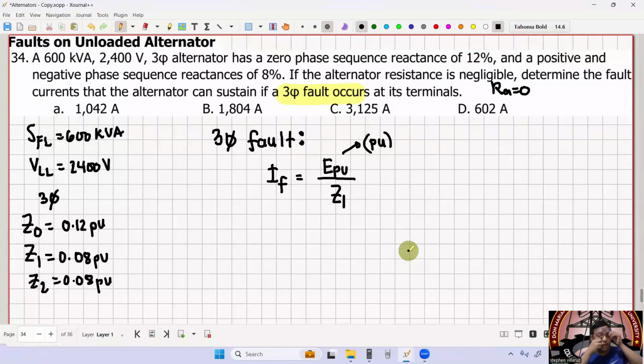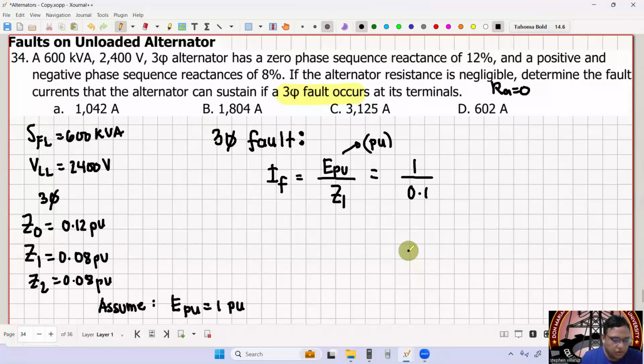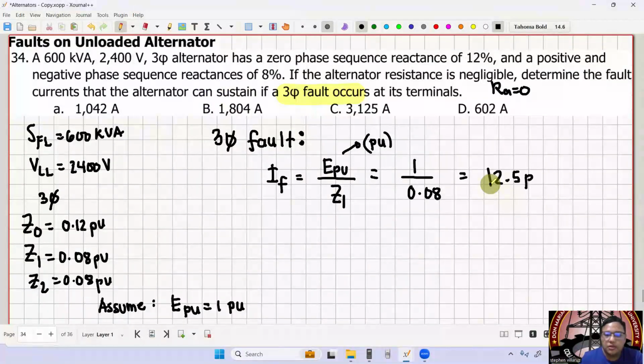Since we have no given pre-fault voltage, we will assume a pre-fault voltage of 1 per unit, as if at rated load. So this is now equal to 1 over 0.08, which equals 12.5 per unit.